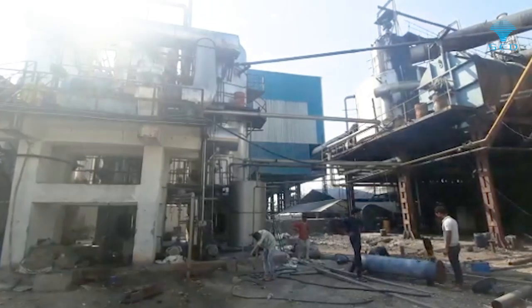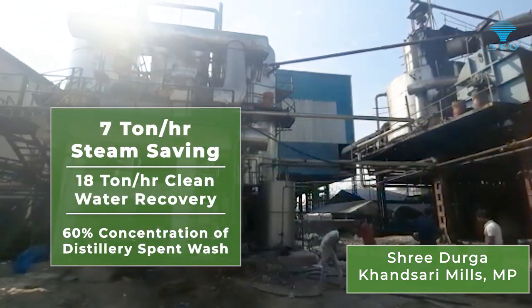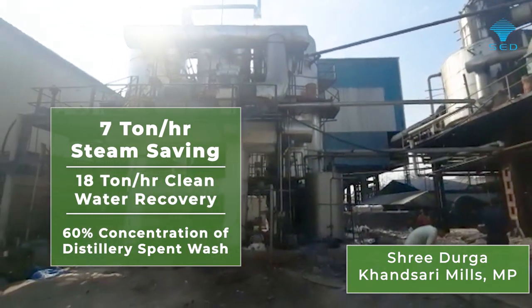We have established 35% to 60% concentration in various installations, clearly indicating the suitability of this technology. We have achieved 60% concentration of distillery waste spent wash in Durga Khandsari Mills, Madhya Pradesh, and in Kibo Sugar, Kenya, with steam savings of around 7 tons per hour and up to 18 tons per hour of clean water recycled back to the process.